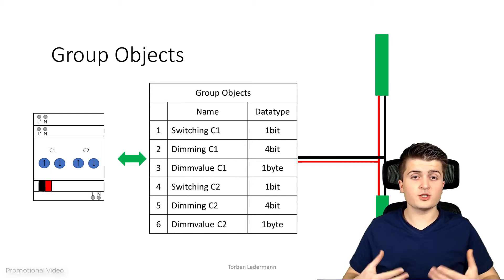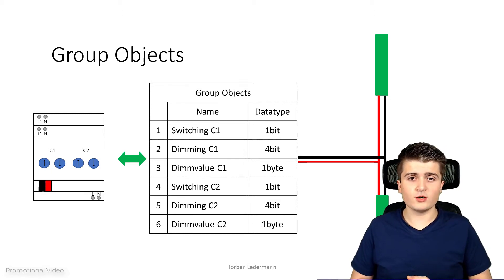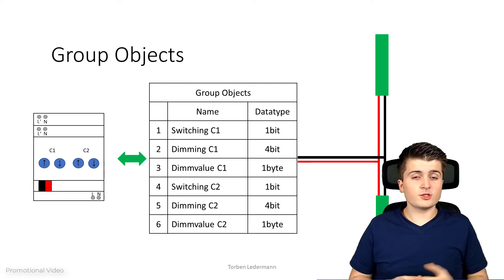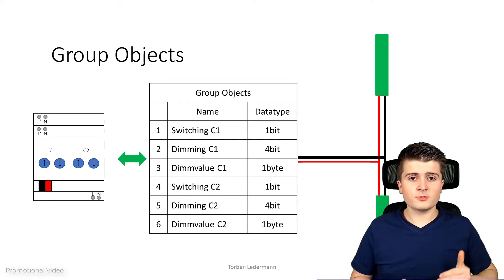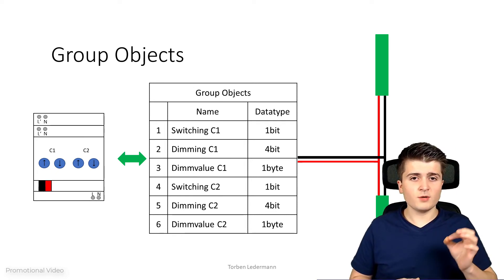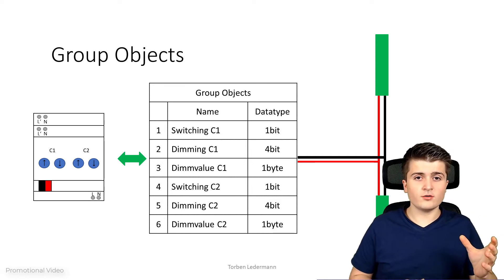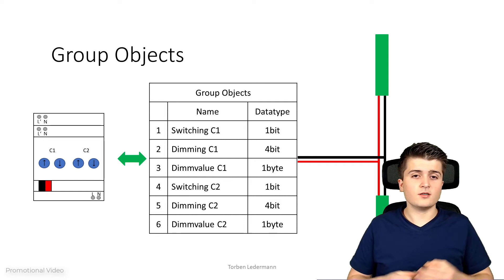In practice we have many more group objects depending on the parameterization of the device and the device itself. For example, in practice we would also have feedback objects, log objects, etc. What you can also notice is that each group object has its own data type. This makes sense because the information for switching is much smaller — it is simply on and off — compared to the dimming value itself, where we need to send a value between 0 and 100%. So each group object has a data type associated to it.